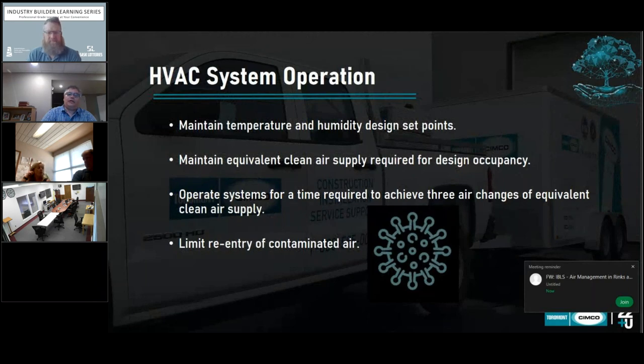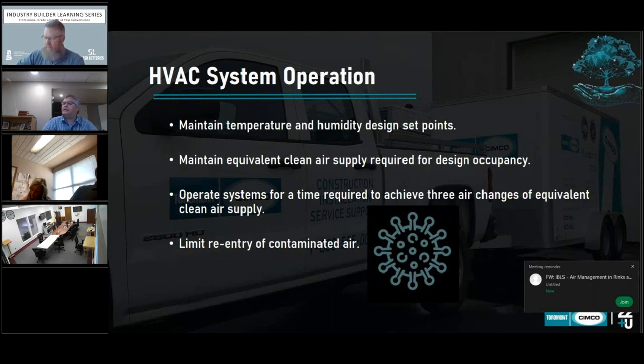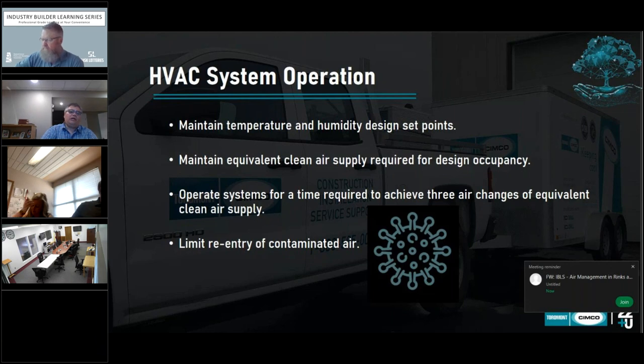So then it boils down to your HVAC system. How do you operate it? Well, you have guidelines and parameters around temperature and humidity set points. Balance your system between clean air and supply air. Operate your systems for a time required to flush out your space, 3 air changes. For a lot of facilities, they'll turn the HVAC system on when they open the doors, and turn it off when they leave at the end of the day. This may mean you're going to have longer run times. In some cases, you may need to run 24/7.